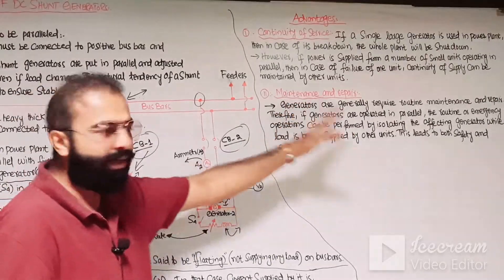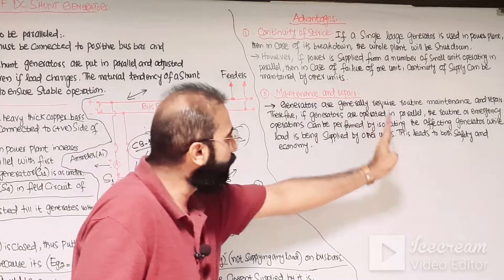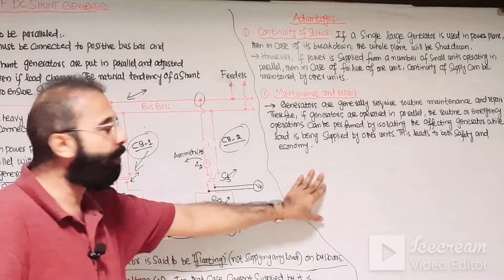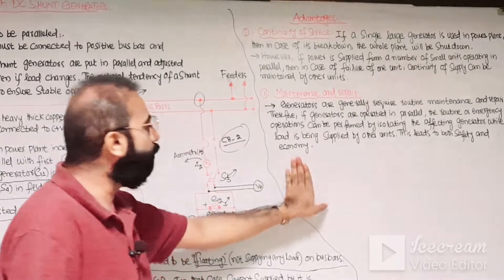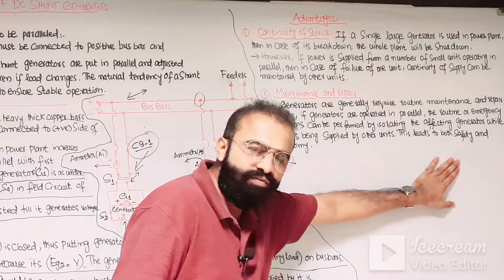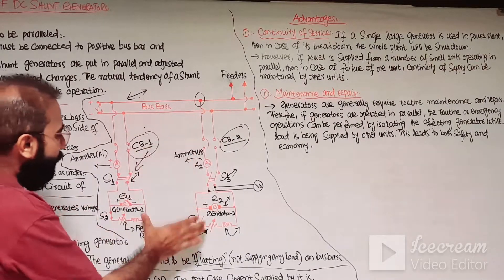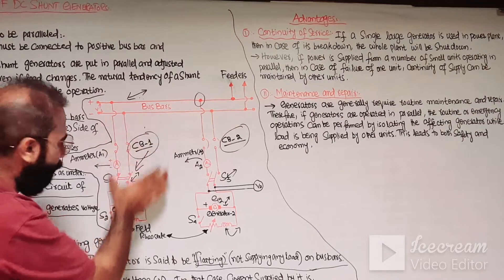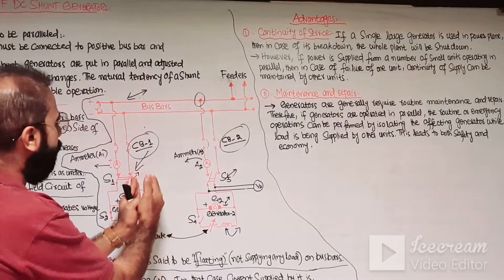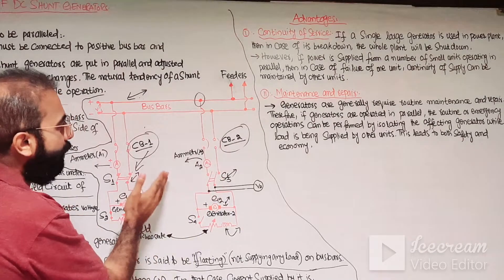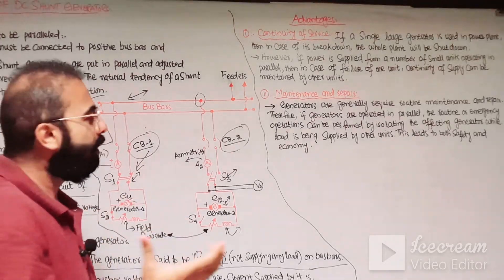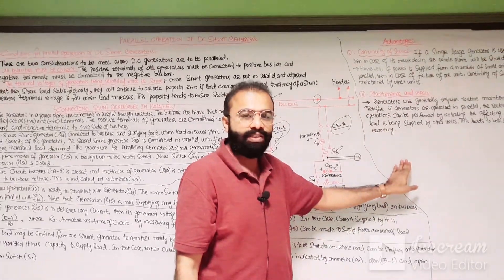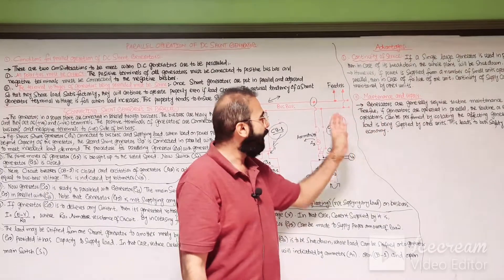The second advantage is maintenance and repair. Generators generally require routine maintenance and repair. If generators are operated in parallel, routine or emergency operations can be performed by isolating the affected generator while the load is being supplied by the other unit, leading to both safety and economy. For example, if maintenance is required on G1, isolate G1 and G2 continues supplying load to the bus bar.